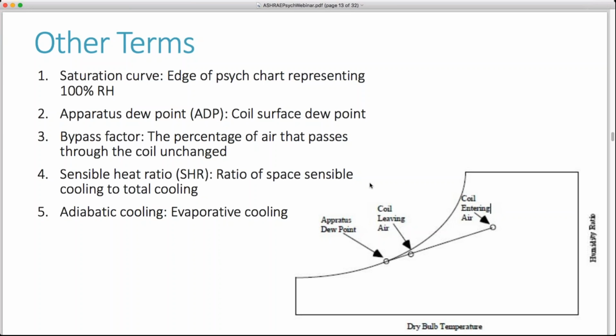I actually had to relearn this one. This can be a little confusing sometimes. The apparatus dew point is basically the coil surface dew point temperature required to accomplish cooling and dehumidifying. So as you can see from the simple psychrometric chart, the air entering the coil is cooled to slightly less than 100% saturation. However, if you want to extract water out of the air or dehumidify, then you need to approach the 100% saturation curve, and that is what's called the apparatus dew point, which is here.